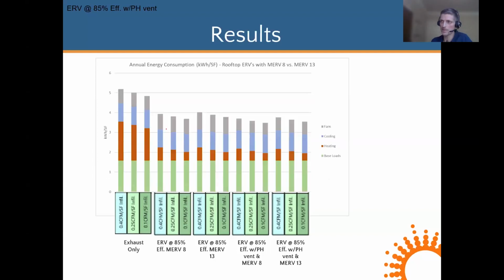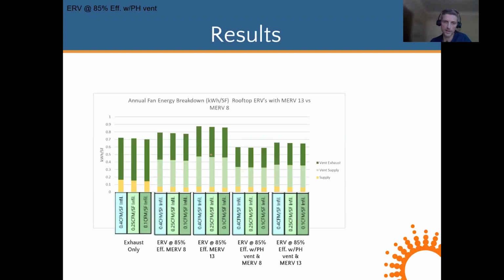So based on this small increase in energy consumption from MERV 8 to MERV 13, we can safely say that moving to MERV 13 filters with any ERV effectiveness would still result in lower energy consumption for rooftop ERVs over the exhaust-only scenario.